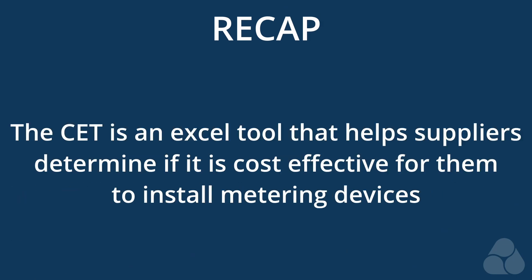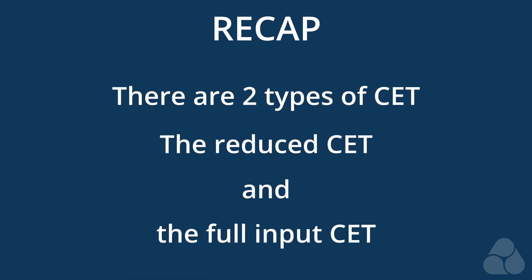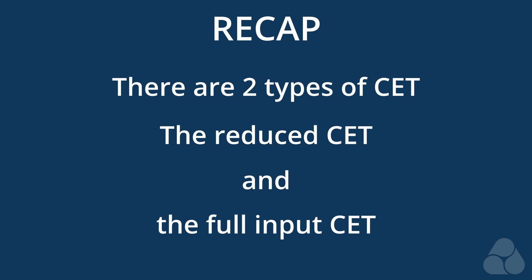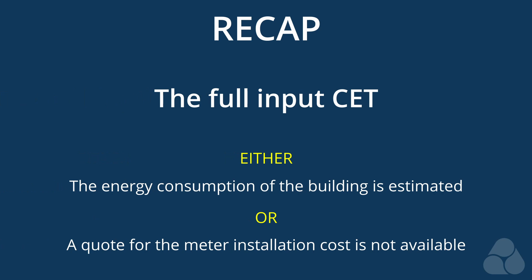To recap: the CET is an Excel format tool designed to help heat suppliers determine if it is cost-effective to install metering devices. There are two types of CET — the Reduced and the Full Input. The Reduced CET is to be filled out when both the actual energy consumption of a building is known and a quote for meter installations is available. The Full Input CET is to be used when the energy consumption of a building is not known and/or a quote for the installation of meters is not available.